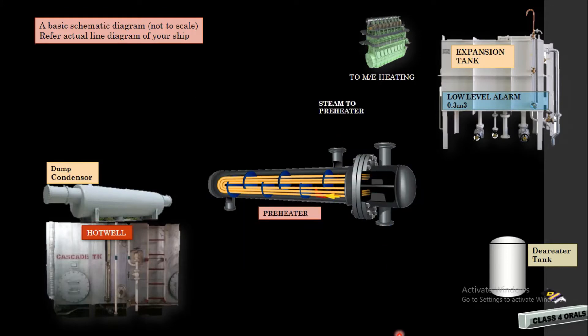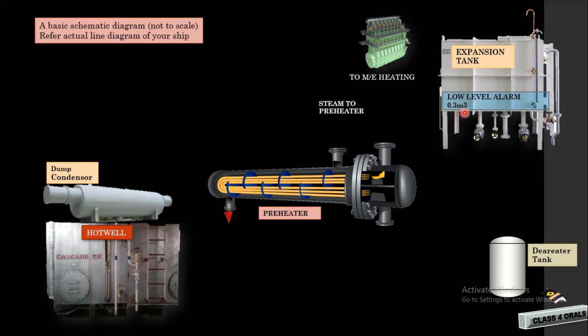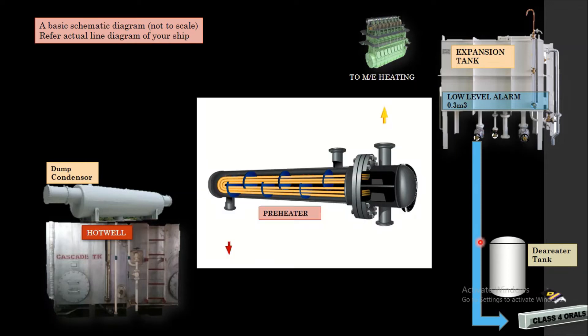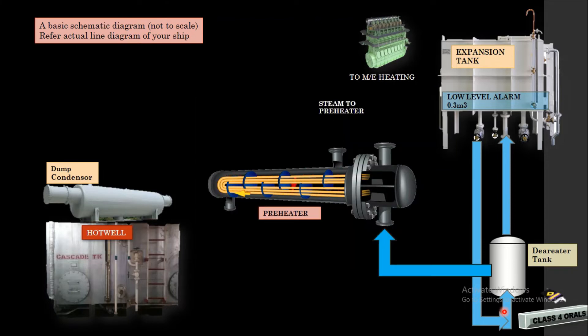Here you can see a basic schematic diagram — please refer to the actual line diagram of your ship. On the right, you can see the expansion tank with low level alarm at 0.3 cubic meters. Here you can see the main engine heating and the preheater. Here you can see the cascade tank provided with the dump condenser, and this is the de-aerator tank. From the expansion tank, water goes to the de-aerator and back. From the de-aerator, a line of jacket cooling water goes to the inlet of the preheater, which goes to the main engine heating.